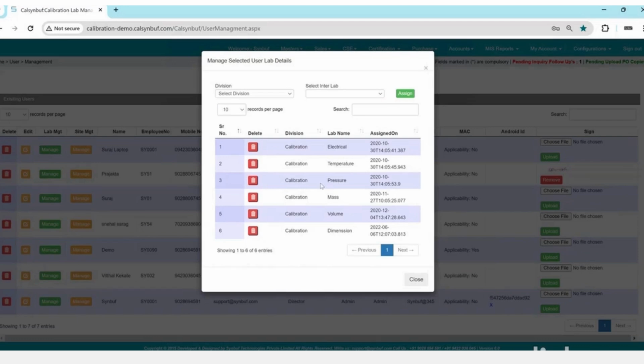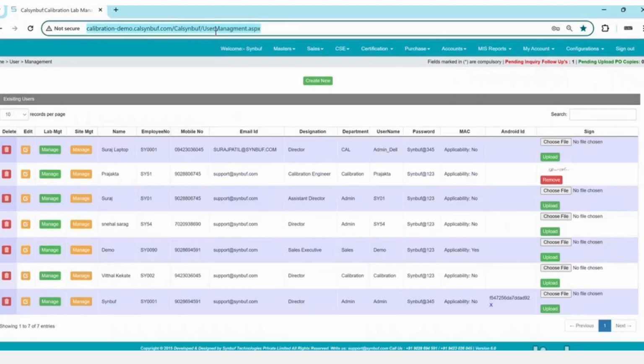If I do not have access to pressure, then I cannot prepare reports of a pressure gauge, vacuum gauge, pressure transmitter, etc. This mapping is based on user expertise and signing authorities. I have logged into this system, and if I try to log in from another system, then this login will expire.